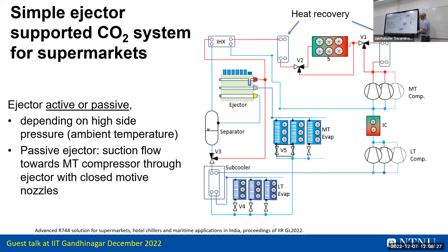What we also want to challenge, and we have challenged the biggest supermarket company here, but they have been bought by somebody else, and now it's a bit of a pity, is the chiller for the supermarket. Typically, it is a double indirect system, meaning you have the water loop for providing the 12/7 water. Then you have the refrigeration system, and then you have the heat rejection loop towards the cooler. So you're penalizing the system everywhere.